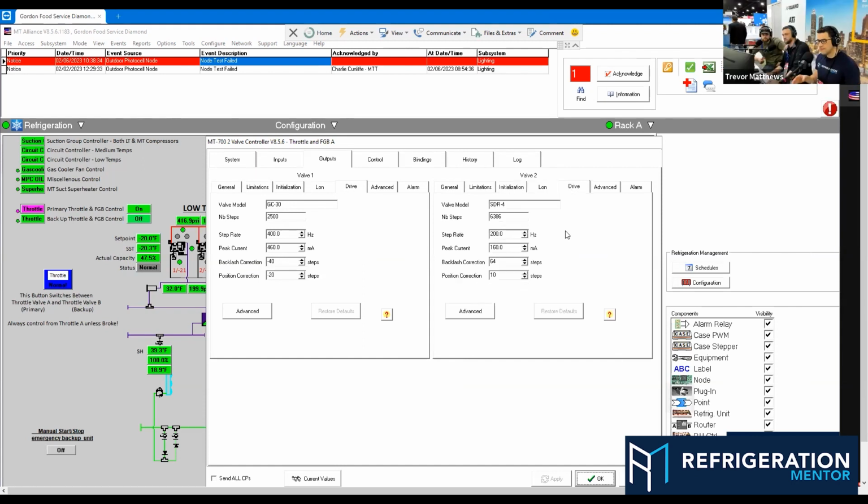And this is what's really important. It's key that you go in and understand each one of these. Yep. You don't want to be going around and changing anything unless you know what each thing does, because if you go in and start just changing the step rate, that's going to affect a bunch of things. If you check the current, it's going to affect it. So don't just start changing stuff unless you know what you're changing and why. And if you do test it, make note of all this stuff, log it. So if anybody else goes there, they know that this is what you changed, so they can go back and put it back to those settings, because a lot of times, like Brett said earlier, things get changed and there's something else wrong in the system. So just make sure you log that stuff.